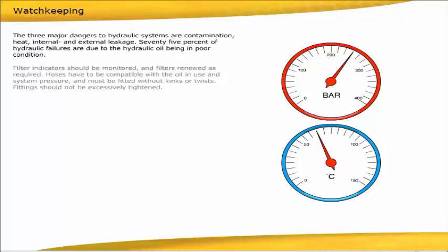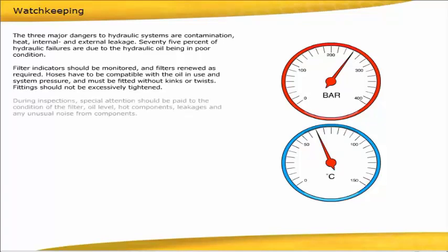Filter indicators should be monitored and filters renewed as required. Hoses have to be compatible with the oil in use and system pressure and must be fitted without kinks or twists. Fittings should not be excessively tightened.